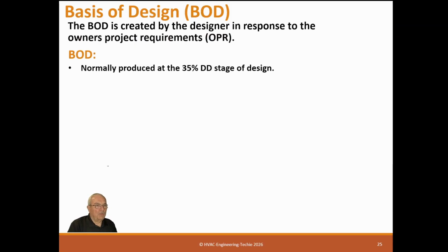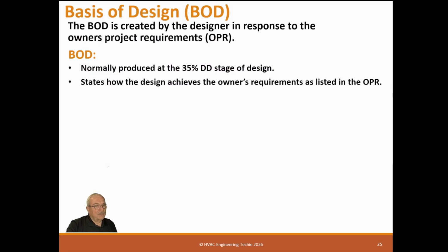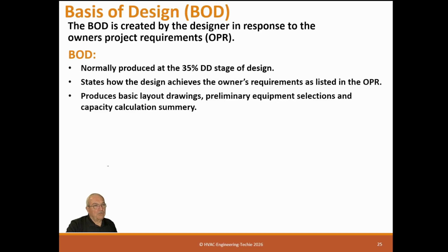Basis of design, normally produced at the 35% DD stage of design, states how the design achieves the owner's requirements as listed in the OPR, produces basic layout drawings, preliminary equipment selection, and a capacity calculation summary. And of course, this would be your 35% submittal.